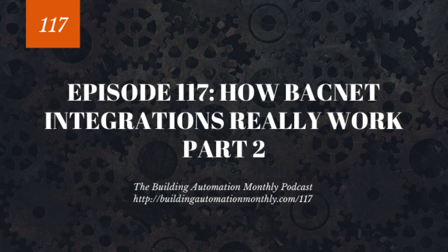Basically, what happens is when you have the token, you're the only one who can talk, and that message goes all the way down the trunk. It's not stopping at each individual controller, unless it has to for messaging purposes, but that's way outside the scope of this episode. So, like I said, RS-485 is using daisy chain, and it's sending those bits in series down the wire. And then we have what is called baud rate.